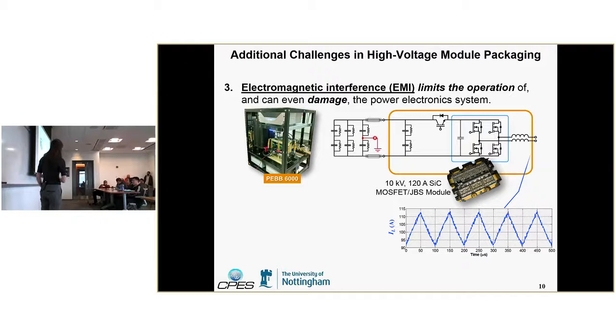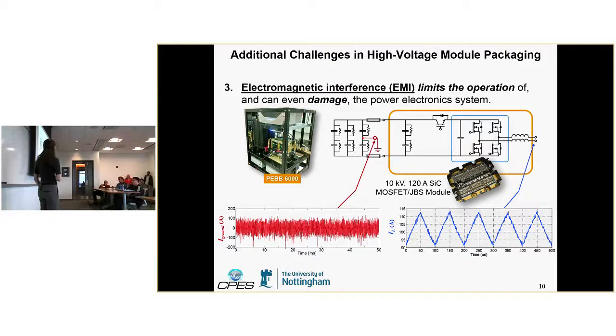So when we were operating, we had about 100 amps average current on the load. And on the current through the ground, we were getting peaks of 200 amps peak to peak flowing through the system ground. So it was quite significant. And part of the reason is that this power module package was designed for silicon IGBTs that switch more than an order of magnitude slower than these silicon carbide MOSFETs. So now you've got the same amount of capacitance for much higher dV/dt. So now you can get more than tens of amps of current flowing through this parasitic capacitance to your heatsink, which is grounded for safety purposes. And so then that will couple through your control circuitry. So that's also something that needs to be considered.